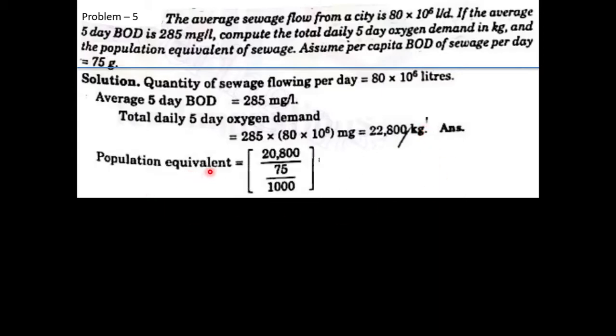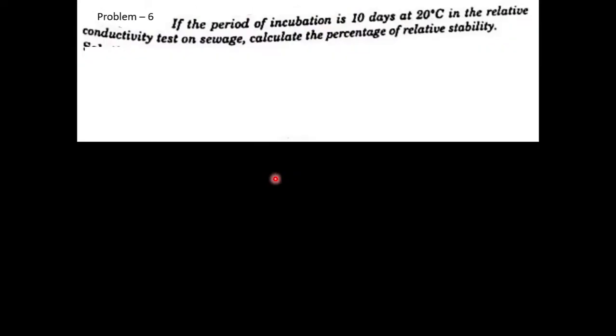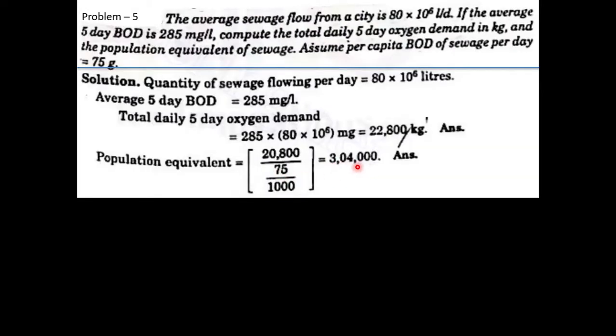Population equivalent = BOD of industrial sewage ÷ standard BOD of domestic sewage per person per day. Per capita BOD = 75 grams = 0.075 kg ≈ 0.08 kg per person per day. Therefore, population equivalent = 22,800 ÷ 0.075 = 3,04,000.